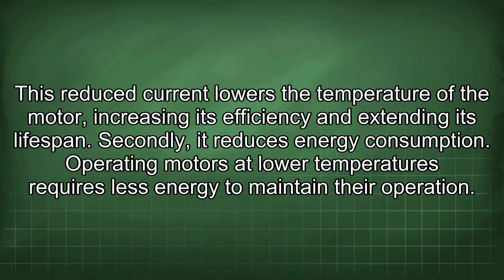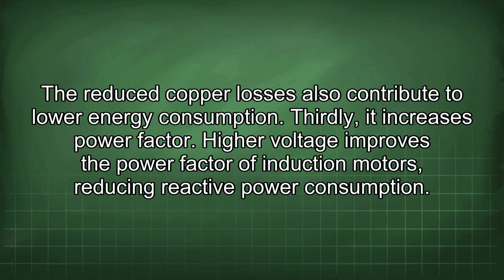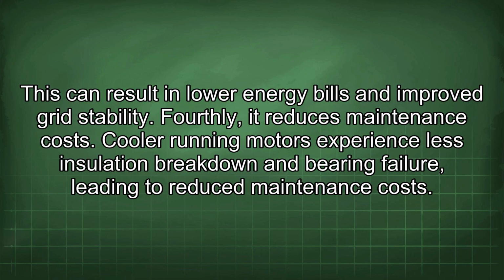Secondly, it reduces energy consumption. Operating motors at lower temperatures requires less energy to maintain their operation. The reduced copper losses also contribute to lower energy consumption. Thirdly, it increases power factor. Higher voltage improves the power factor of induction motors, reducing reactive power consumption. This can result in lower energy bills and improved grid stability.